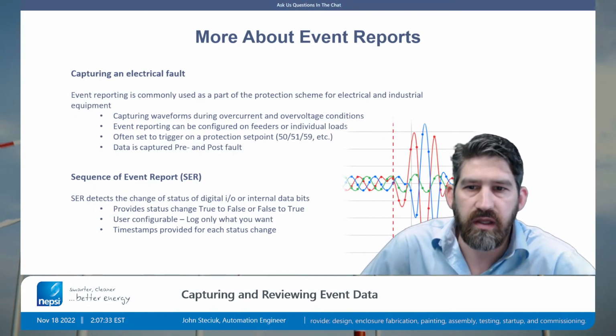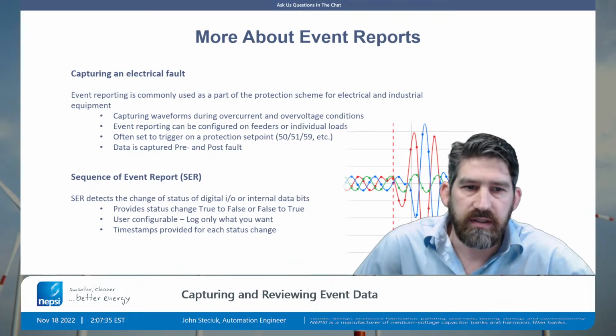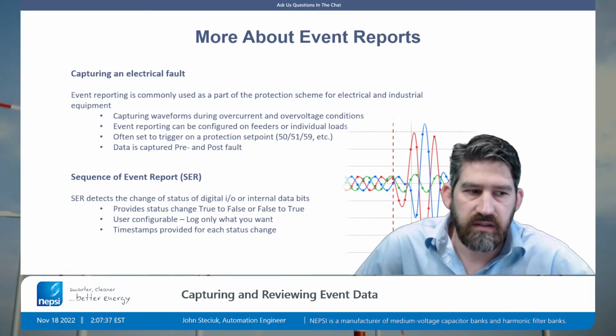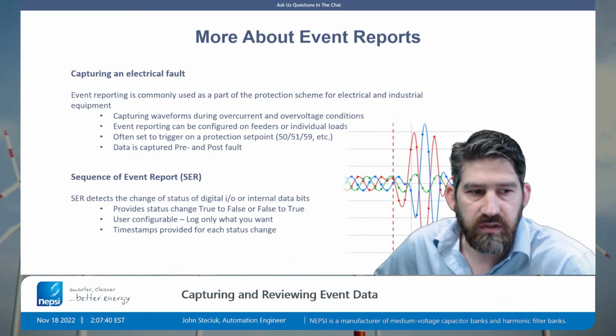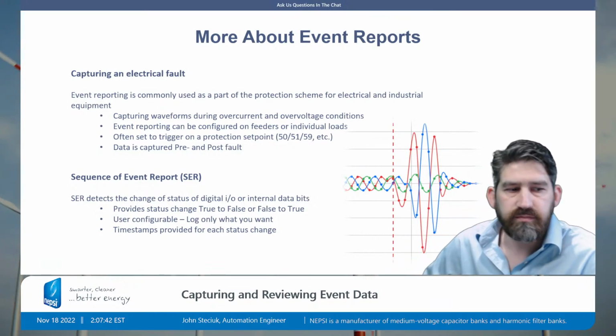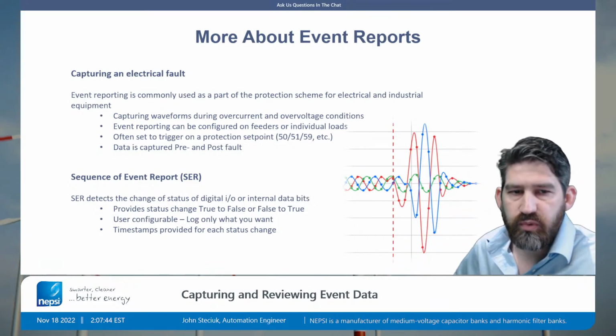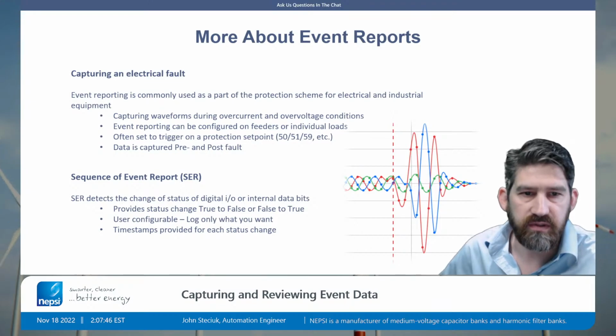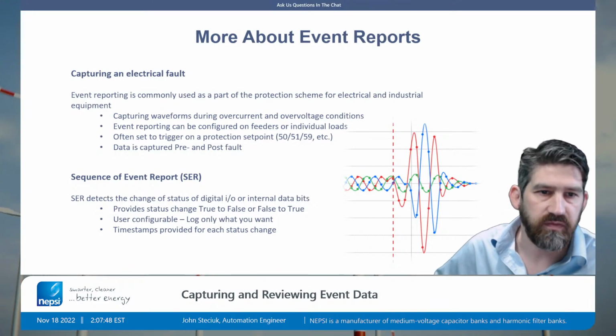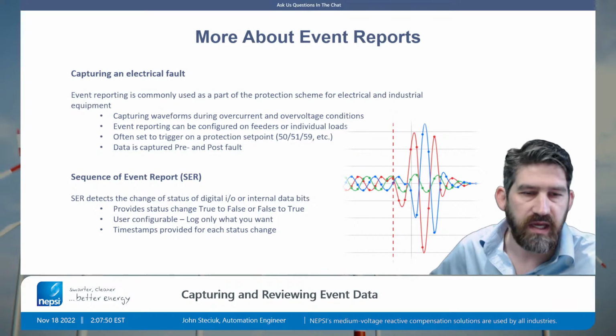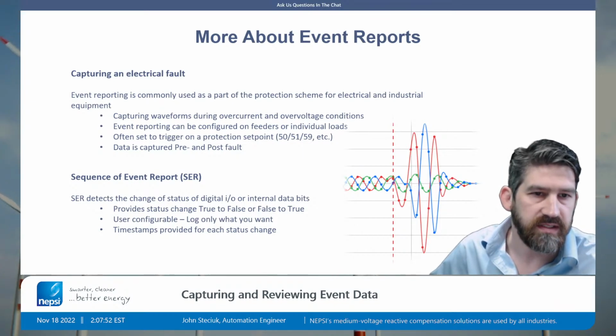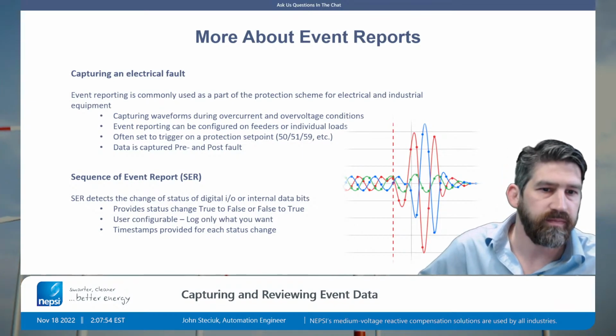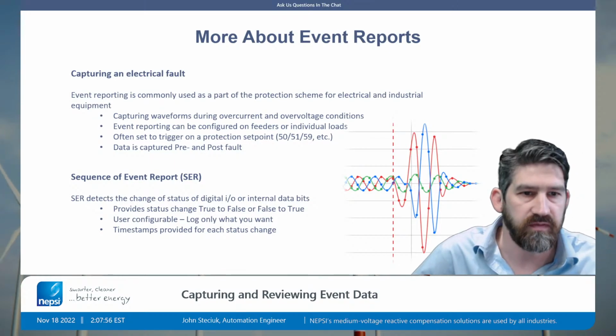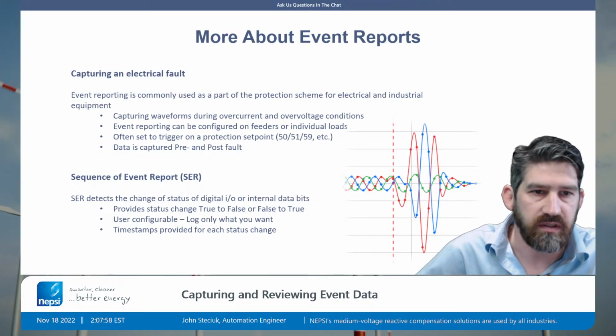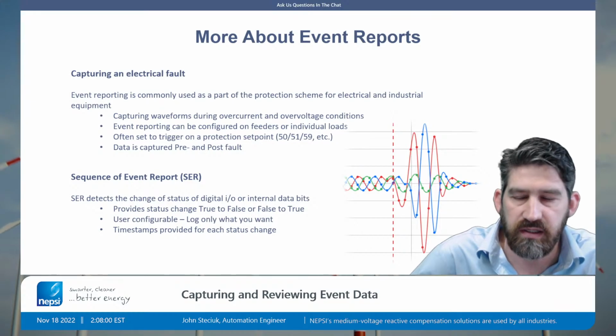high harmonic value. And as you can see in the image to the right here, we've got pre-fault data to the left side of the red dashed line, and then that dashed line represents the event, and after the event, there's data. You can see the current spikes enormously high.